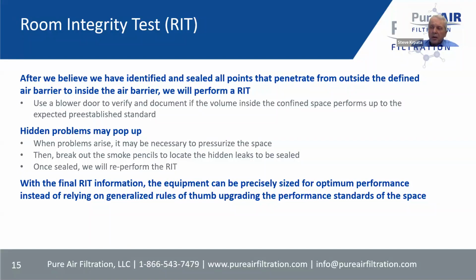But if it doesn't test out that way, and on occasion there are, even for experienced crews like ours, things that are hidden. Like I said, if there are sheetrock walls and different construction things, it gets trickier trying to find things, and we may have to use other methods. We may have to use smoke pencils, when we have the board on and the room is pressurized, to find where the particular leaks are. Then we can seal that, go back, do another room integrity test, and know that we have found all the problems and have gotten them sealed.